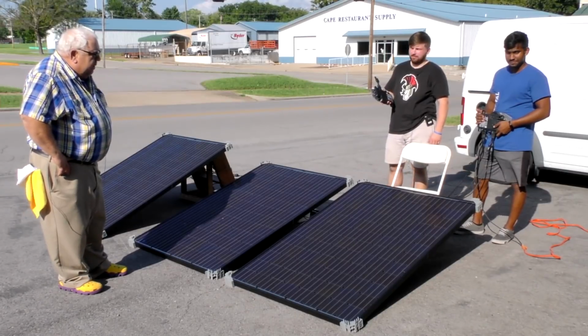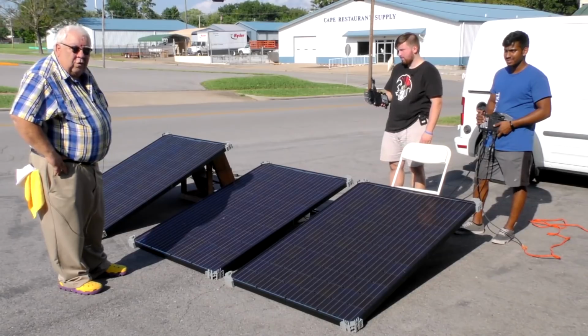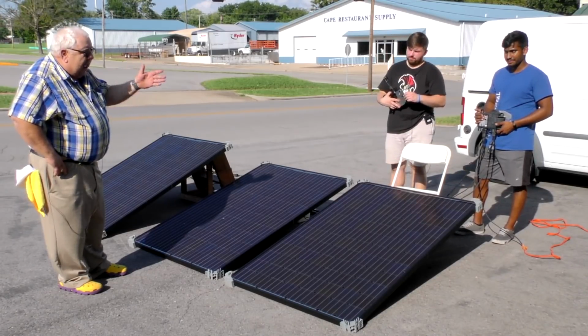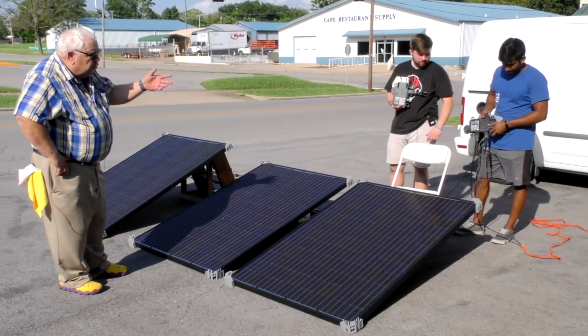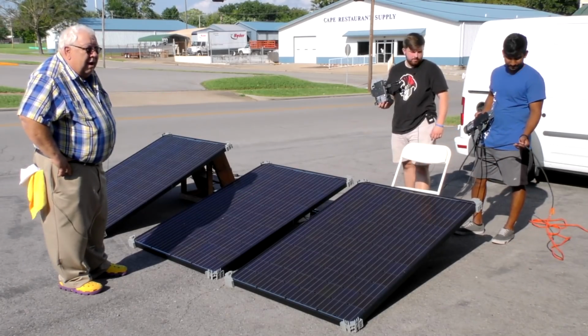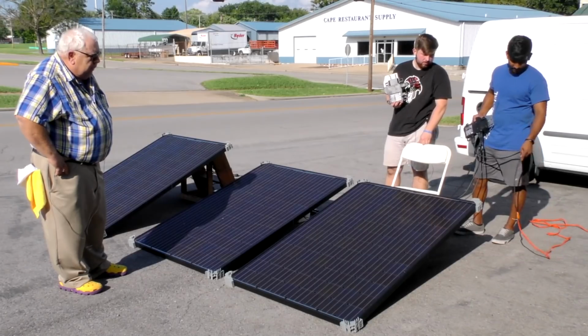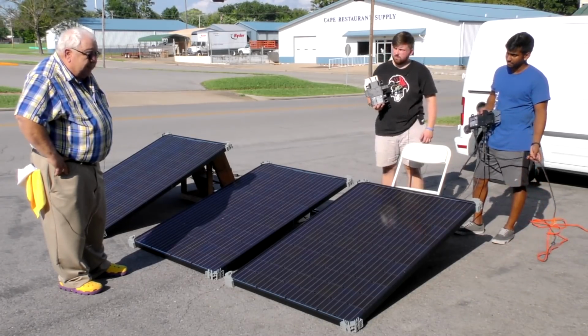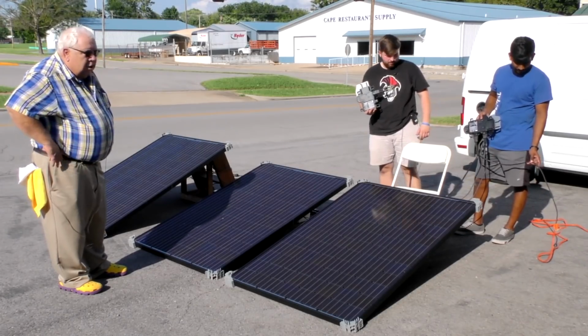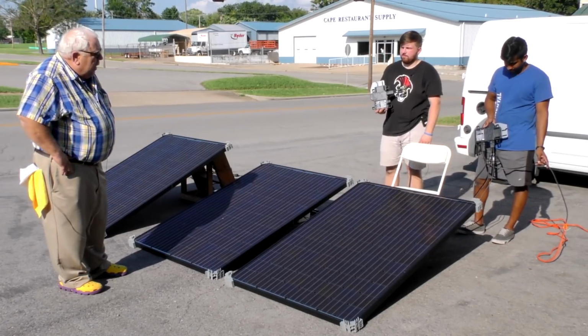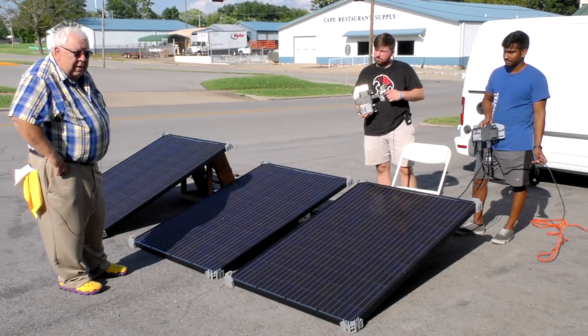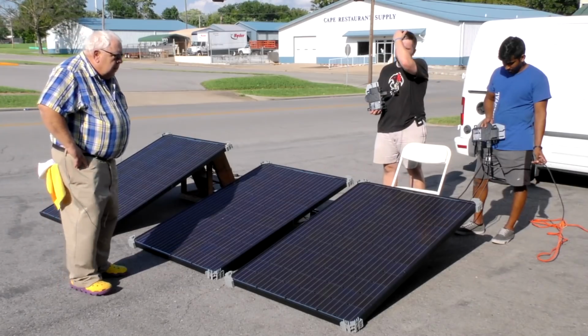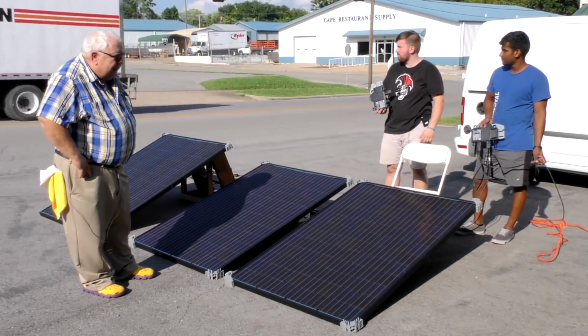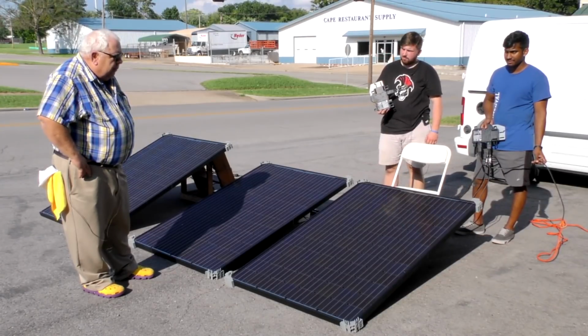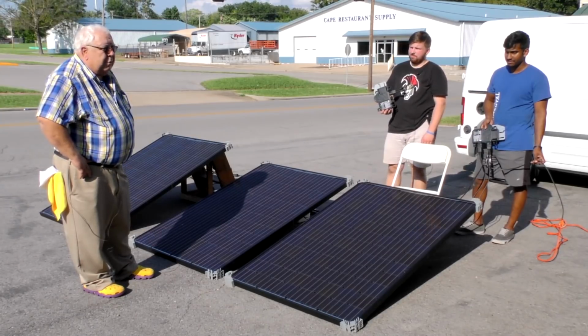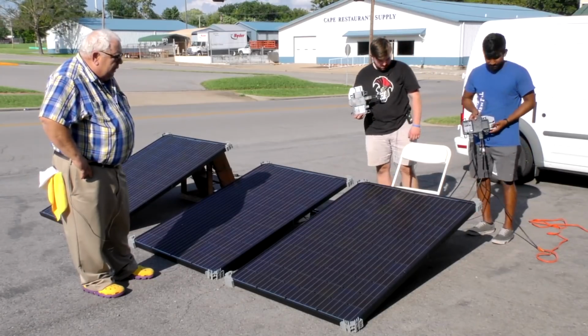We're going to go see if these work the same as our Solar Edge grid-tied inverters. These have to have a 240 volt - this cable is two wires, red and black, right? Yep. And that's a 240 volt output, no neutral. We're going to wire that into our inverter and through the charge enable contactor so we can turn it on and off and see how it works with our inverter to determine if it will charge the batteries in AC coupled fashion, identical to or similar to the Solar Edge, and see if we get some power out of these panels.